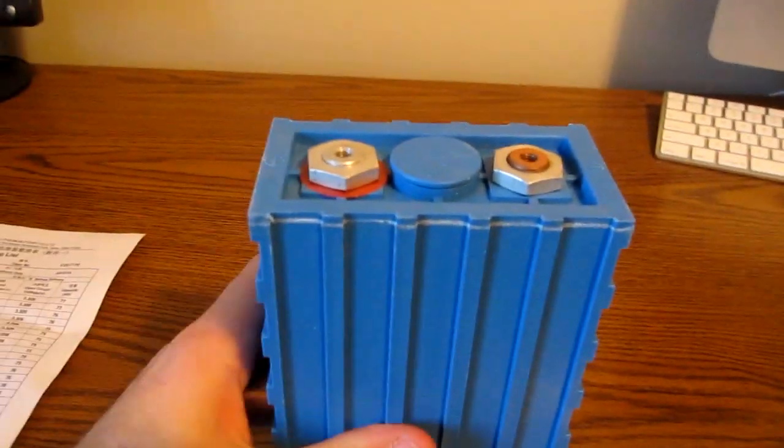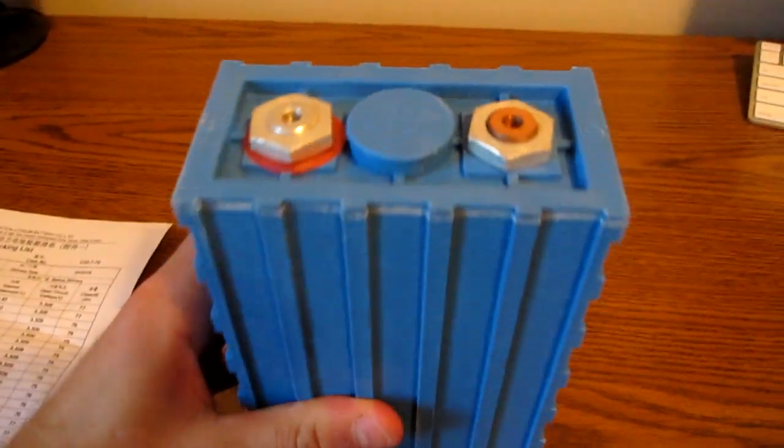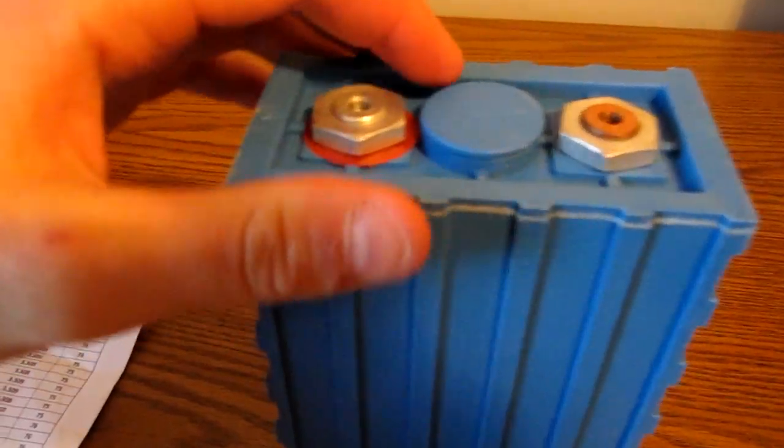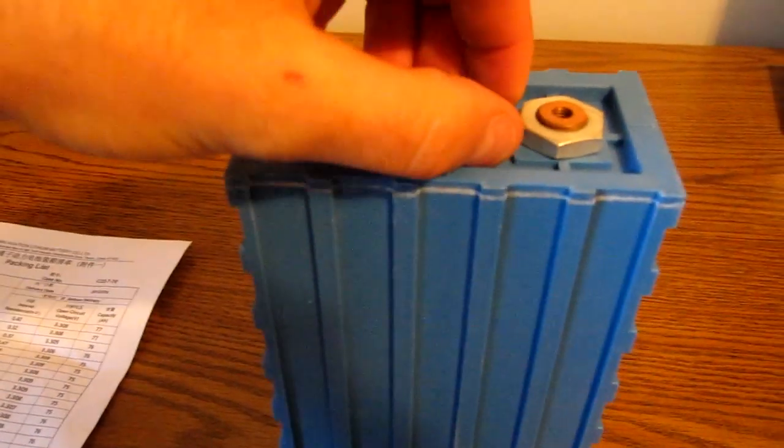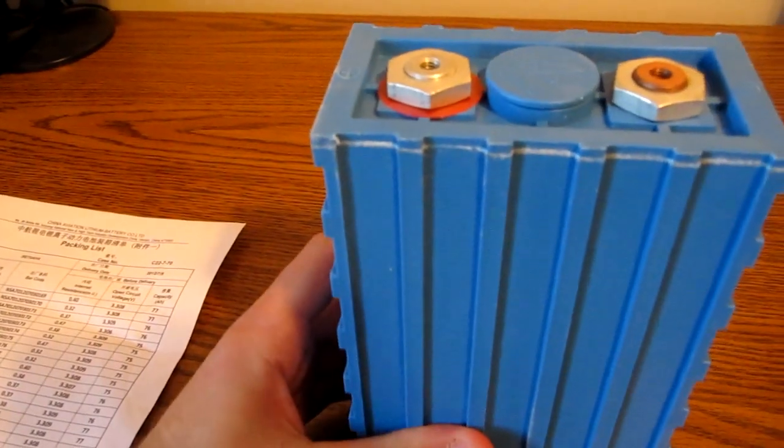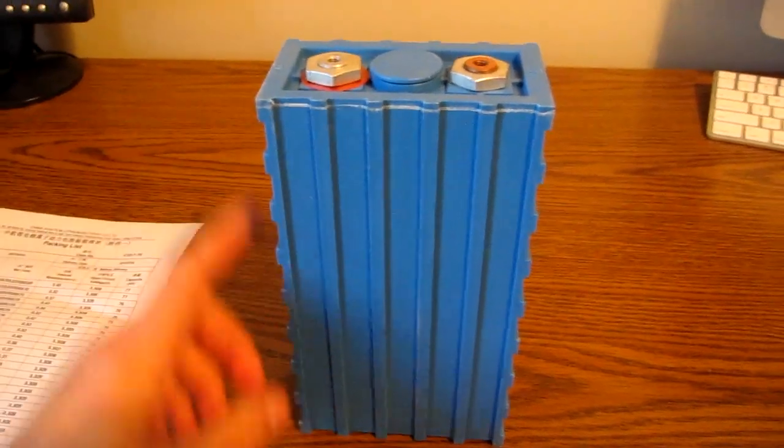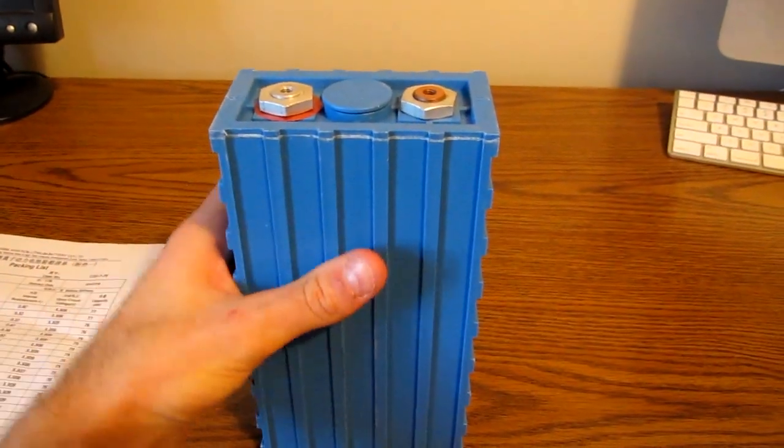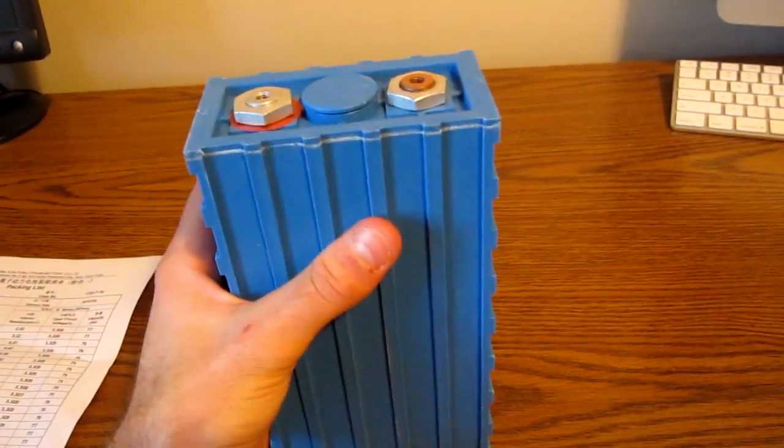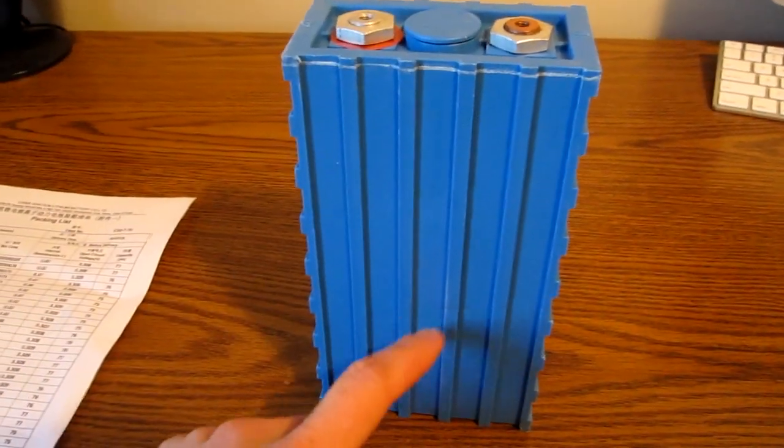So these cells basically have the usual two terminals and here's the vent cap right in the middle here. They recommend that you use these things upright because if you mount them upside down there's a chance that any loose electrolyte in there could leak out of the vent cap.